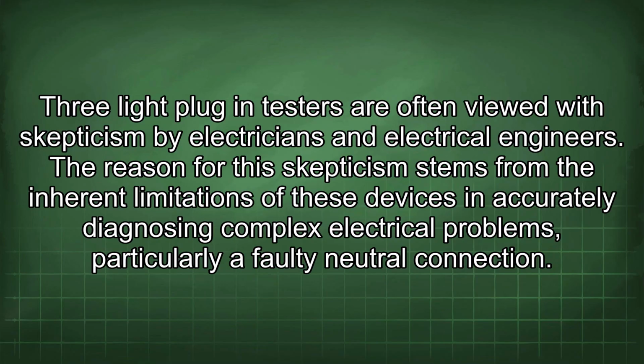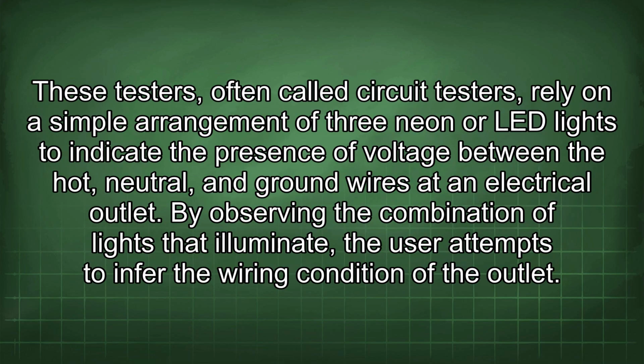3-light plug-in testers are often viewed with skepticism by electricians and electrical engineers. The reason for this skepticism stems from the inherent limitations of these devices in accurately diagnosing complex electrical problems, particularly a faulty neutral connection. These testers, often called circuit testers, rely on a simple arrangement of 3 neon or LED lights to indicate the presence of voltage between the hot, neutral, and ground wires at an electrical outlet. By observing the combination of lights that illuminate, the user attempts to infer the wiring condition of the outlet.